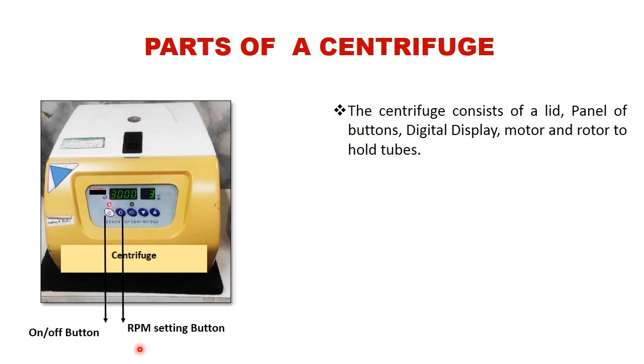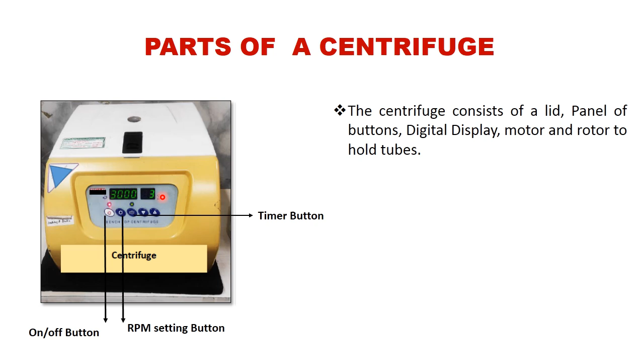The arrows, the triangle upside down and the normal triangle, are used either for decreasing or increasing the speed of rotation or the timing that is required for centrifugation. Now, the rotors which are inside the centrifuge, at a fixed radius away from the motor, are either made of aluminium or titanium alloys. Each of them has its advantage. Aluminium is pocket friendly, that is, it is less costly, whereas titanium is more resistant to erosion by corrosives, acids or temperature.